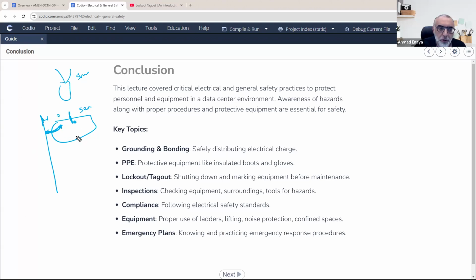What if there is no bonding? If there is no bonding and you put the voltmeter between the chassis and the rack, you will see some floating numbers. I have seen this a lot and tested it sometimes. If you measure the voltage between two devices that are not bonded, the voltage may be a low value or just floating, meaning these devices are not connected together. Anything other than 0 means these devices are not bonded, so it should be short circuit. The good thing is you don't need to measure the voltage yourself, since most voltmeters have a short circuit check.